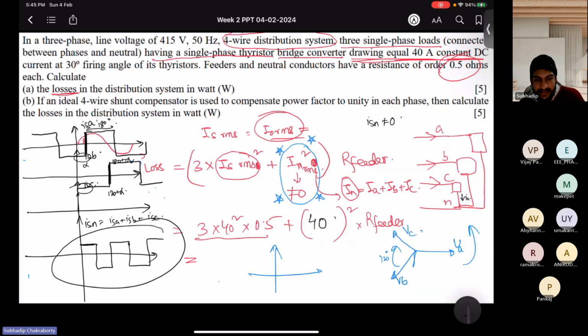That is the main point which I want to make. Because the loss is due to the RMS value, not the average value. The average value of this signal is anyway 0. But the RMS value is not 0. So with the same amplitude, plus 40 and minus 40, the neutral current will also toggle. So the net loss, what are you getting? Just see what value is coming. R feeder is 0.5. So 3 times 40 squared into 0.5.